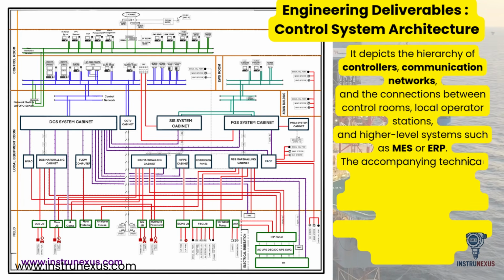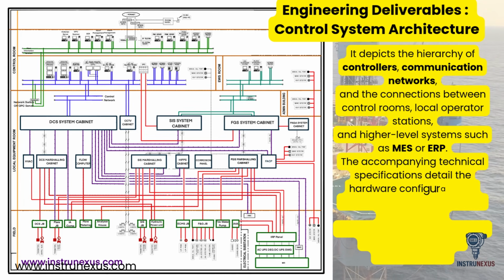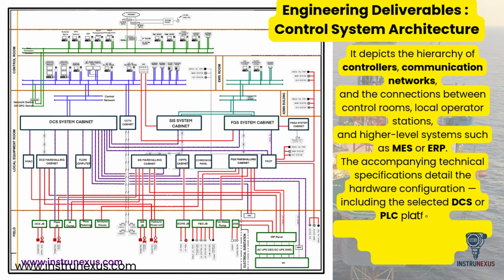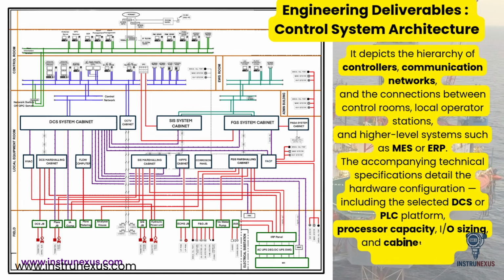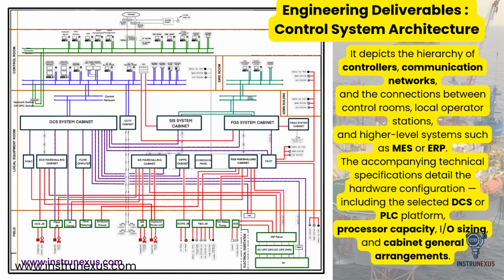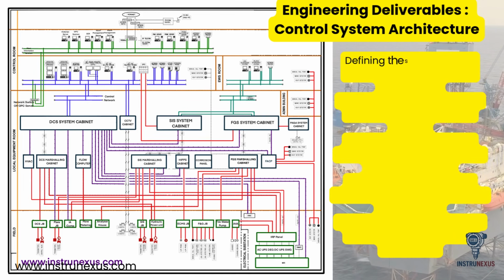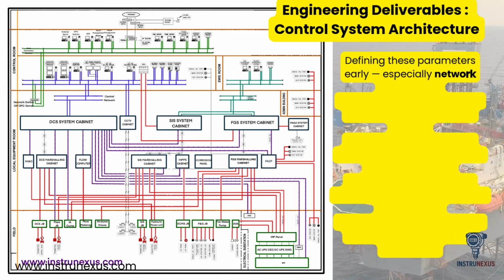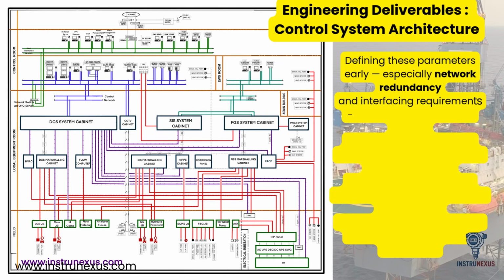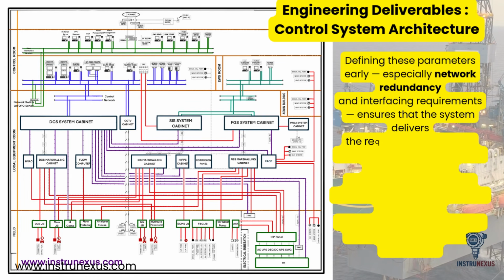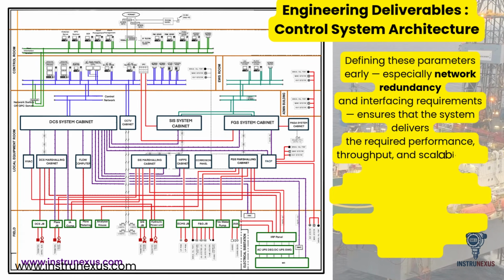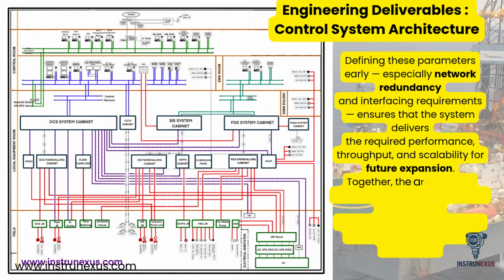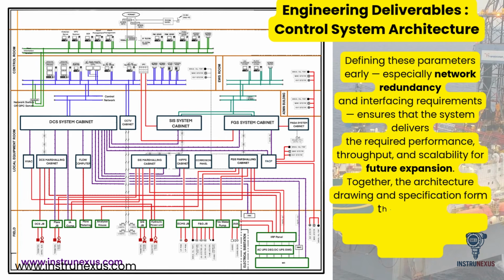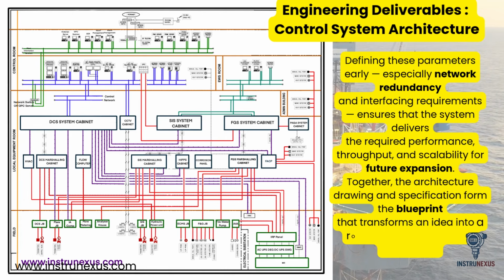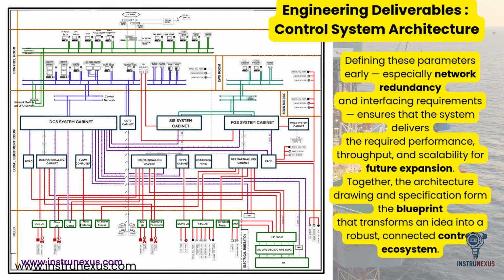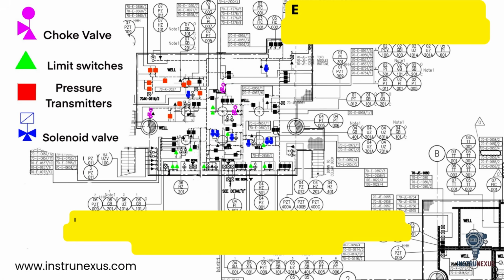The accompanying technical specifications detail the hardware configuration, including the selected DCS or PLC platform, processor capacity, I/O sizing, and cabinet general arrangements. Defining these parameters early, especially network redundancy and interfacing requirements, ensures that the system delivers the required performance, throughput, and scalability for future expansion. Together, the architecture drawing and specification form the blueprint that transforms an idea into a robust, connected control ecosystem.